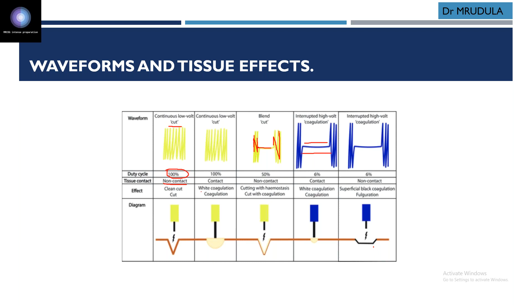Then fulguration, which is a 6% duty cycle. Here the active time is very less, while the off time is high. So there will be no current in between, and the tissue returns to normal temperature. Interrupted high voltage coagulation, if it is 6% with contact, causes coagulation. With non-contact, it causes fulguration or sparking. So these are the differences between different waveforms and their tissue effects.